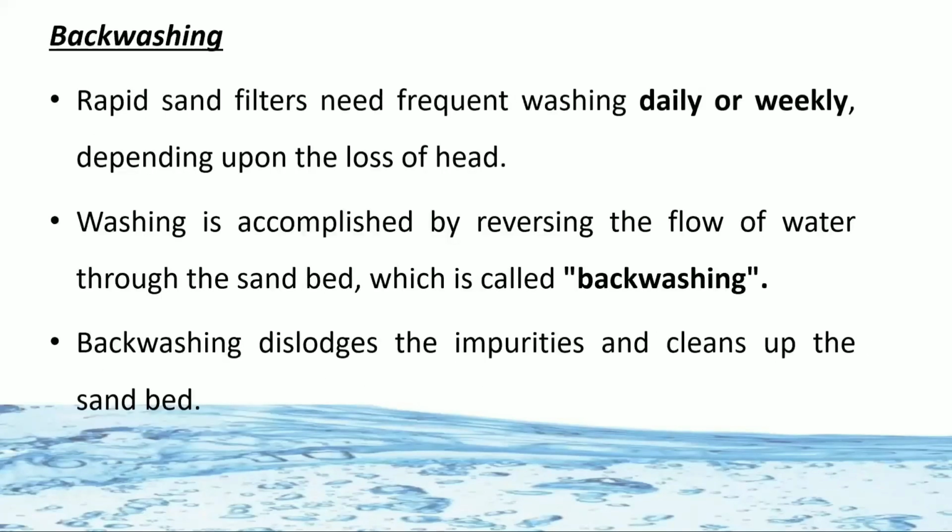So how does backwashing take place? The rapid sand filters need frequent washing. It may be daily or weekly. In slow sand filter, we have seen the cleaning required weekly or after some months. So in rapid sand filter, the cleaning is required daily or sometimes weekly. This washing is accomplished by reversing the flow of water. Means here we have to reverse the flow of water through the sand bed, which is called backwashing. The word itself suggests back, means reverse. Reverse washing.